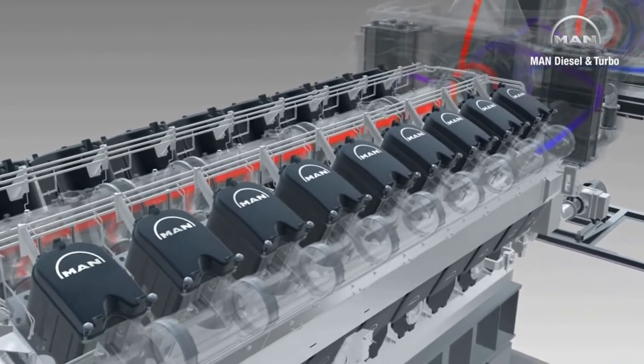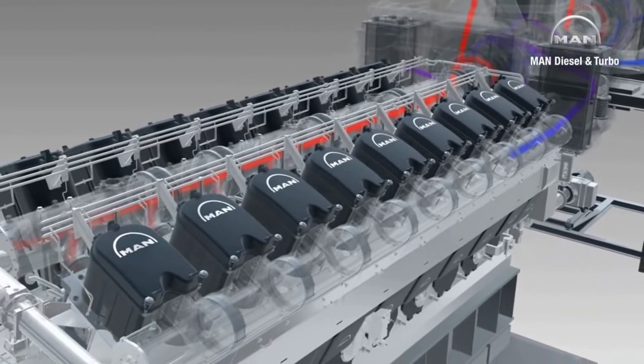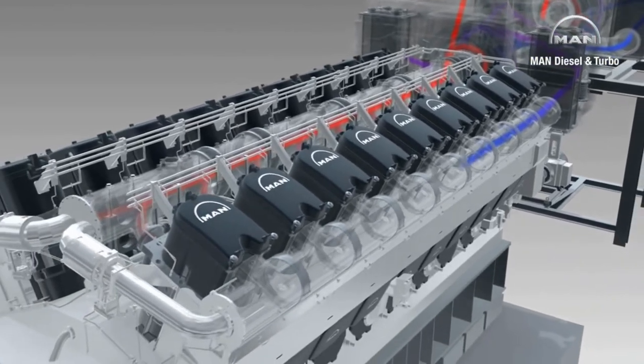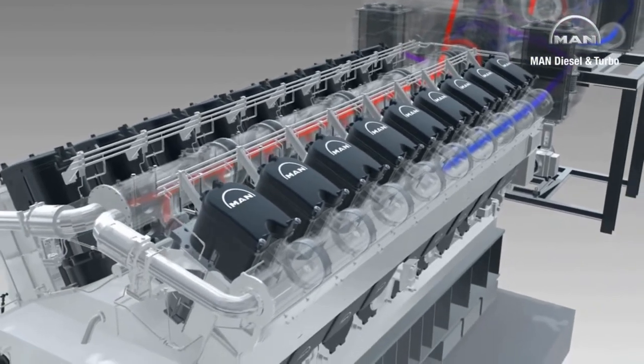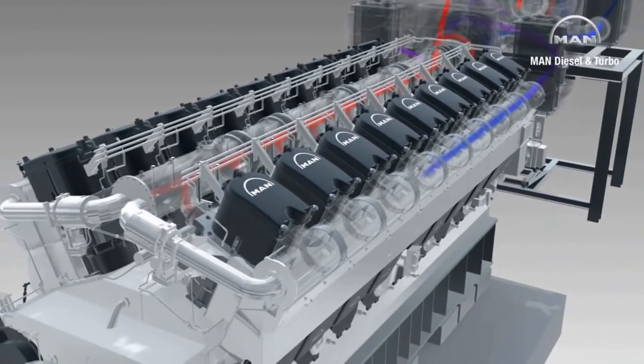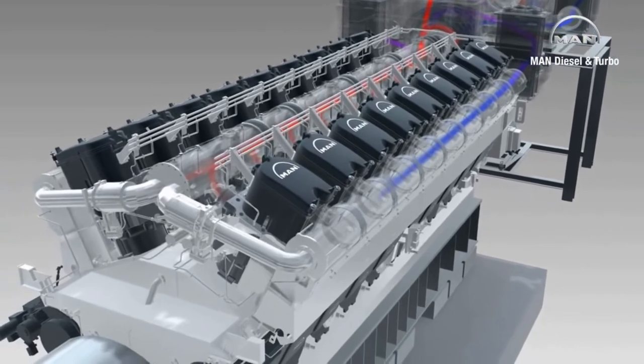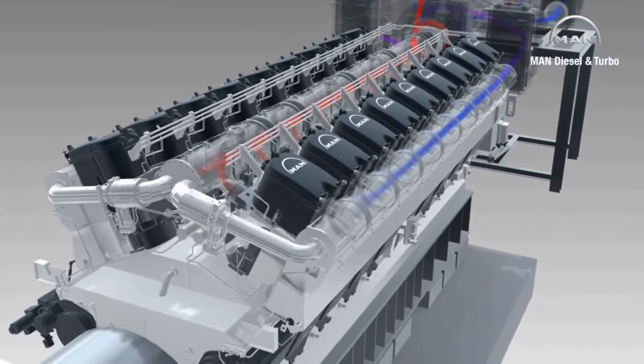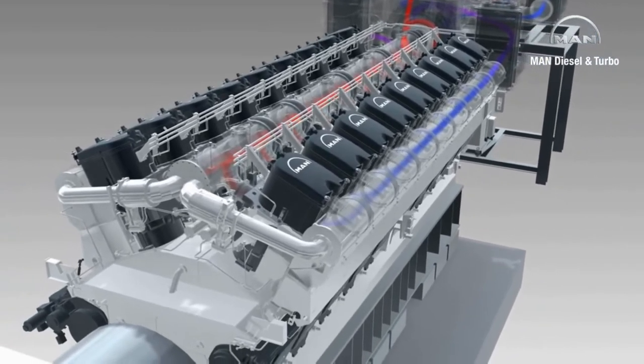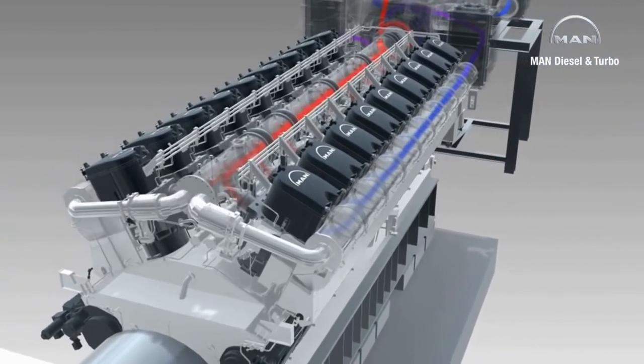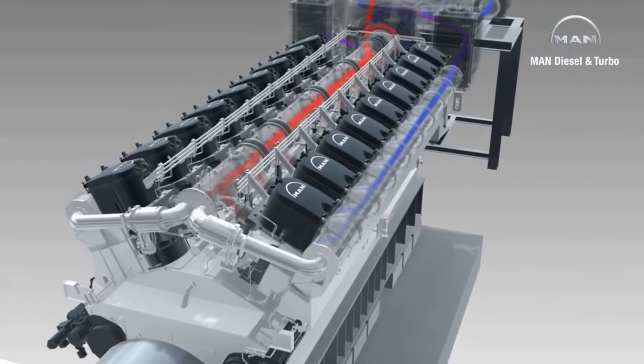Unlike conventional turbocharging, which only permits charge pressures of around 3 bars, the charge air of the 18V4860 TS is delivered to the cylinders with almost 6 bars.